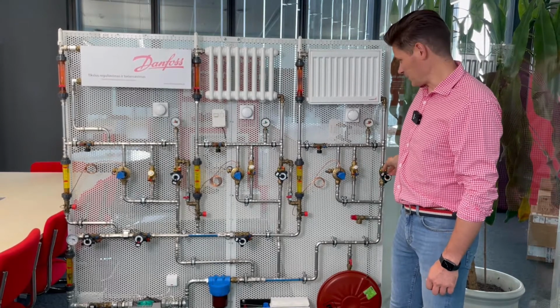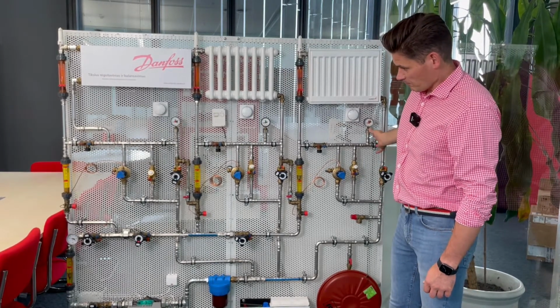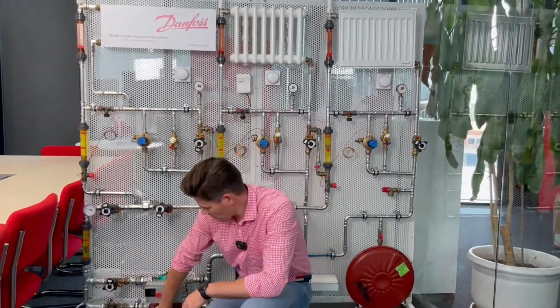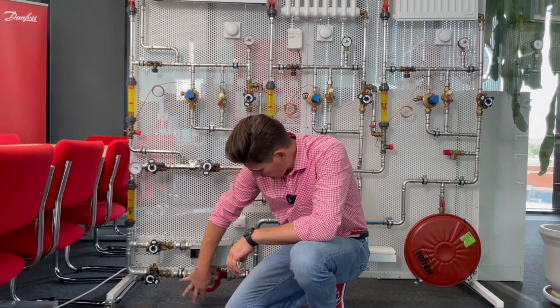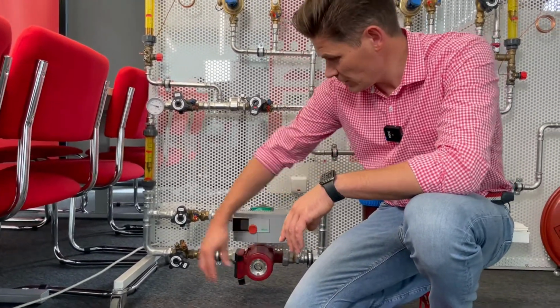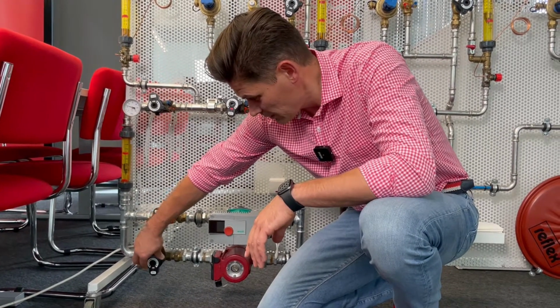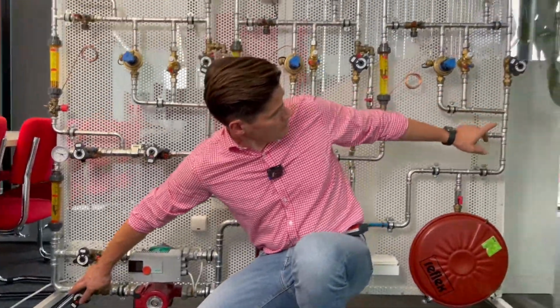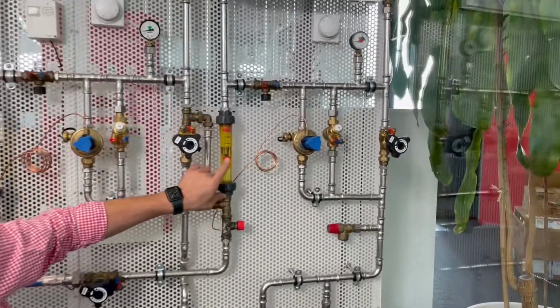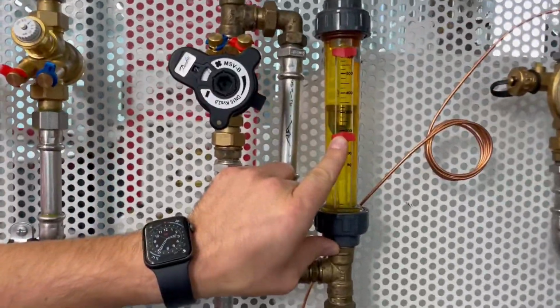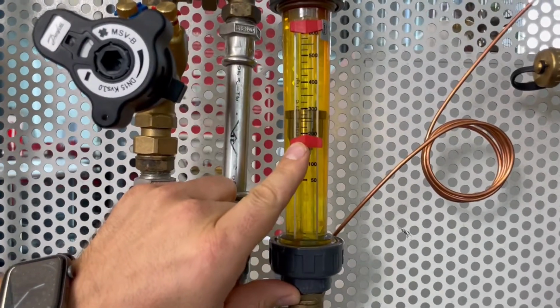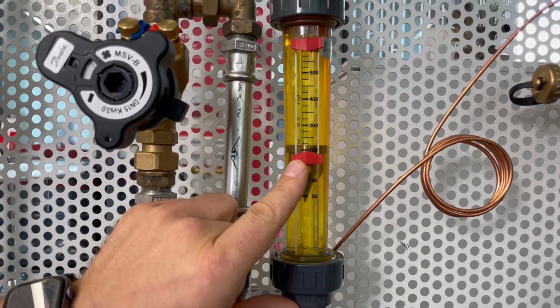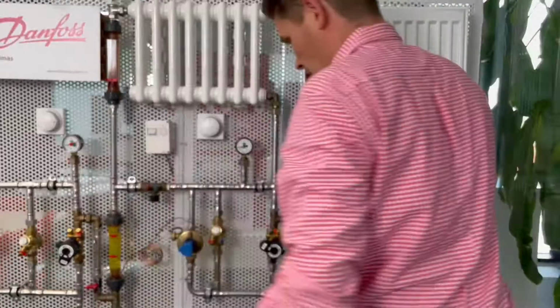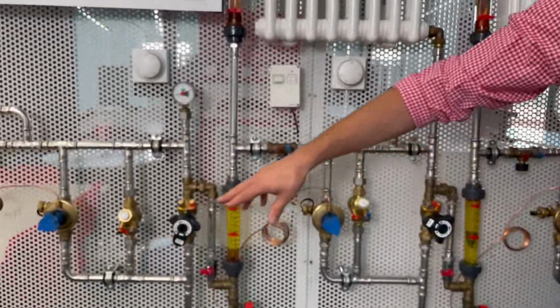Then the sun goes out and clouds come. What do they do? Adjustment of the pump. Here I cannot regulate a lot because it already runs on first gear, or first speed. So I just squeeze the manual balancing valve next to the pump, looking at this flow. I need to set here 200 liters. Okay, I set here 200 liters, my design flow. Let's check all other risers. Here we have 0. Here we have 0. Second riser 0. First one is also 0.